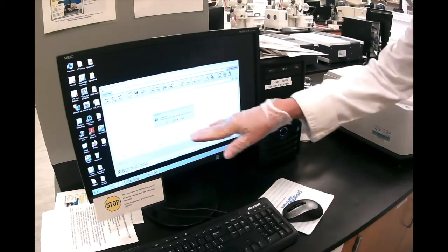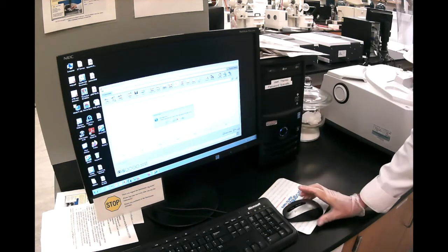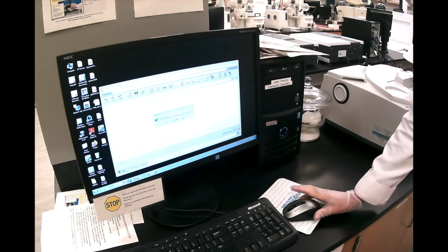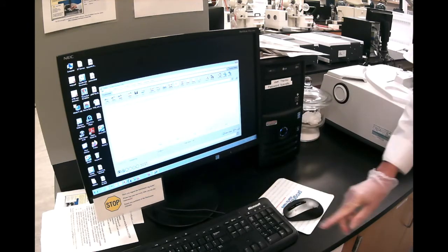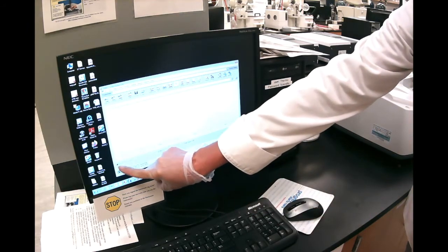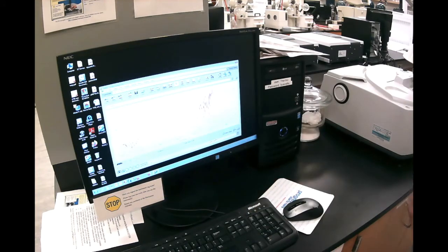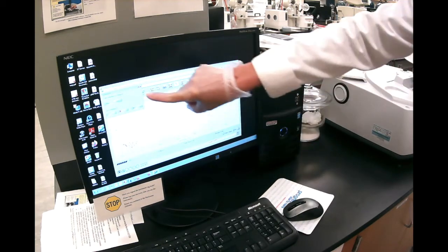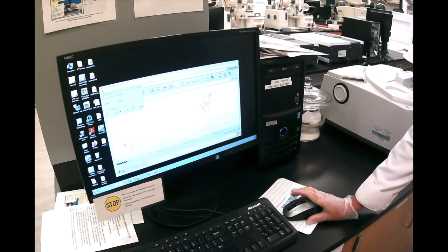on it, and again you have another dialog box. This dialog box means it's talking to you, it's telling you please prepare to collect the background, which means if you didn't clean it, please clean your surface there. And then you say OK, meaning I'm ready. So immediately when you say OK, you will see that it starts to collect with these little bars at the bottom turning blue. And when it's complete, it scans it. There's another dialog box here. It says confirmation, data collection has stopped.